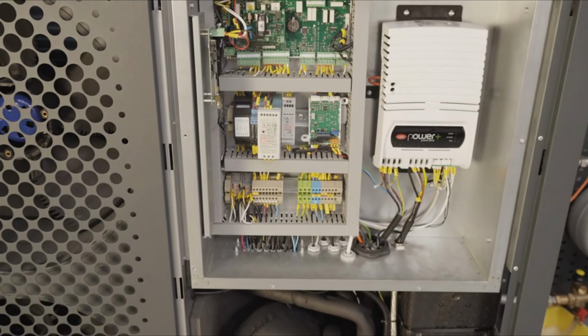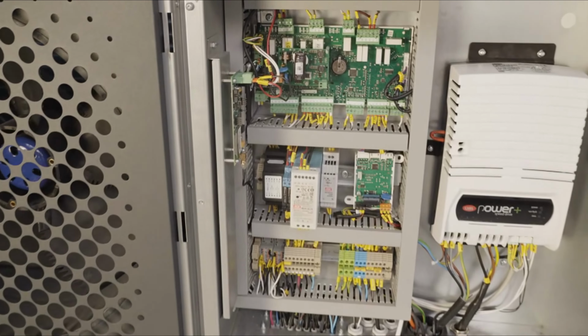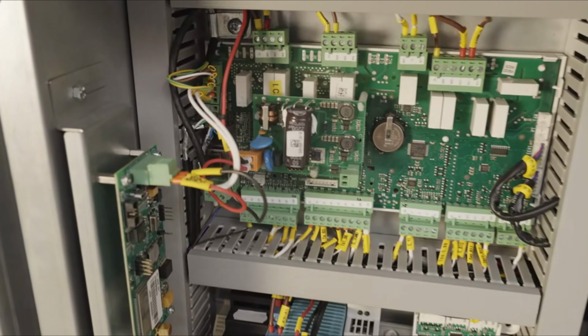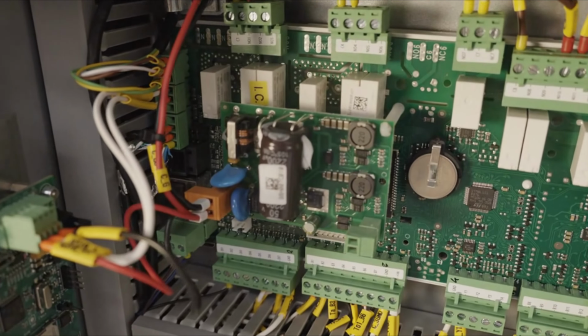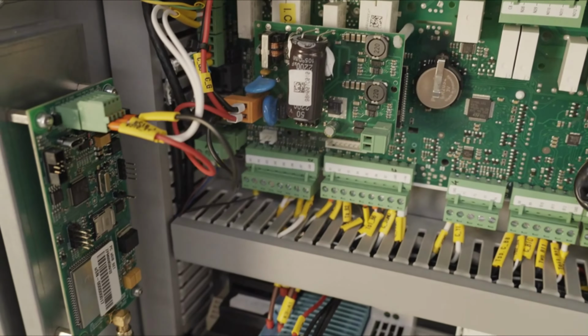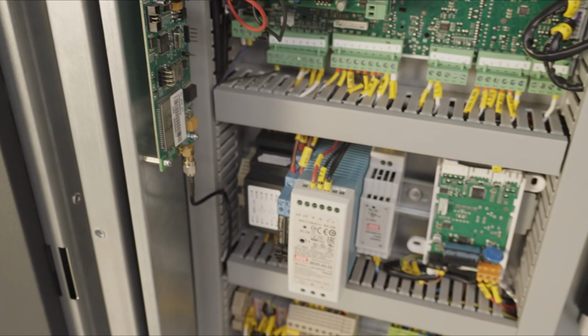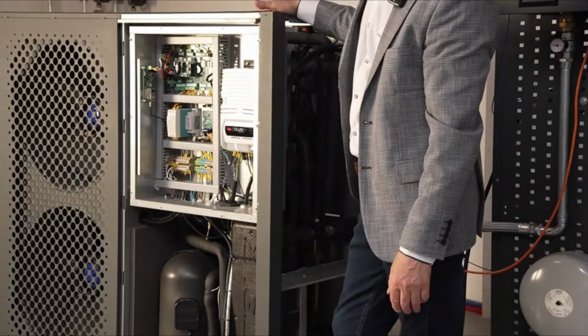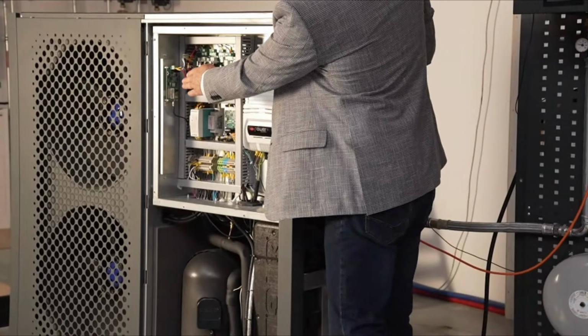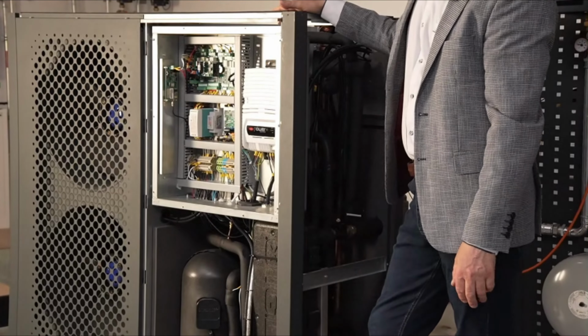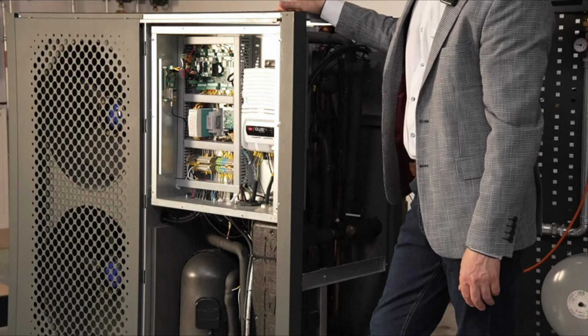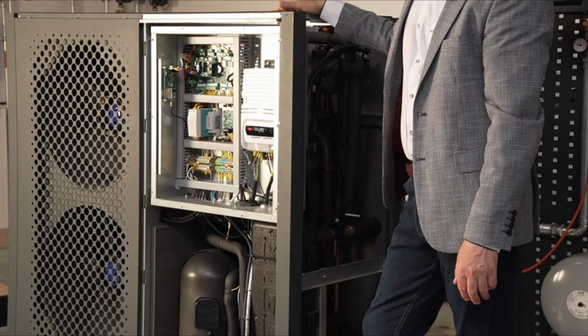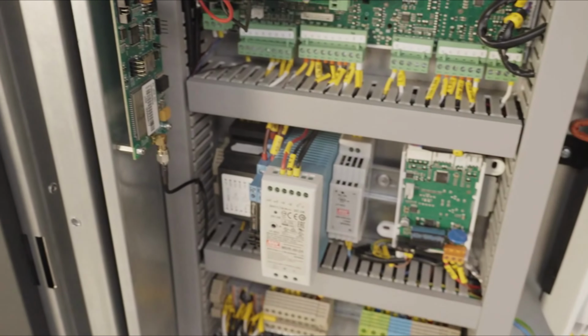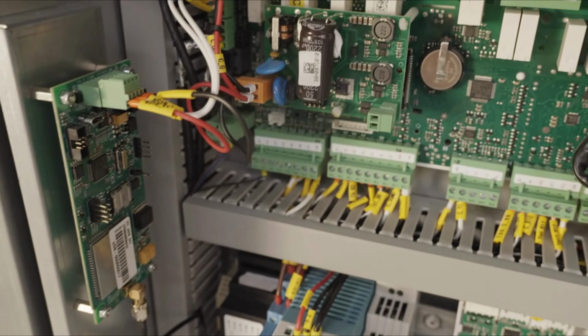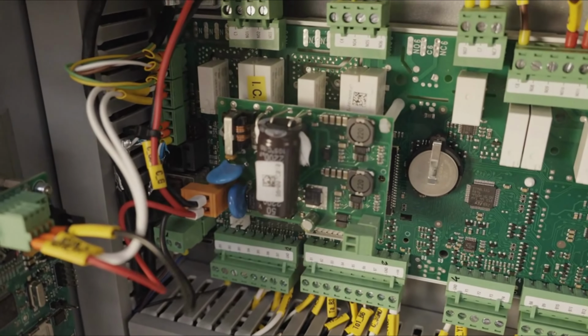So we have the electrical switchboard, the main controller, the LTE communication module, the drive, and accessories for controlling the pump's automation. Each of our pumps comes equipped with an LTE module. This means that as soon as it's plugged into the power supply, it instantly appears in the cloud and we can immediately log into every single one of them. There's no need for any configuration, no Wi-Fi networks, no internet cables.